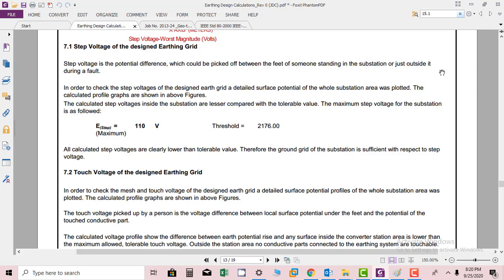All calculated step voltages are clearly lower than the tolerable value. Therefore, the ground grid of the substation is sufficient with respect to step voltages. Hence it is proof that the grid that we have designed is acceptable.